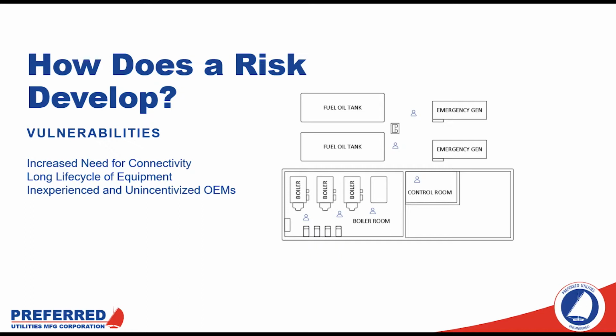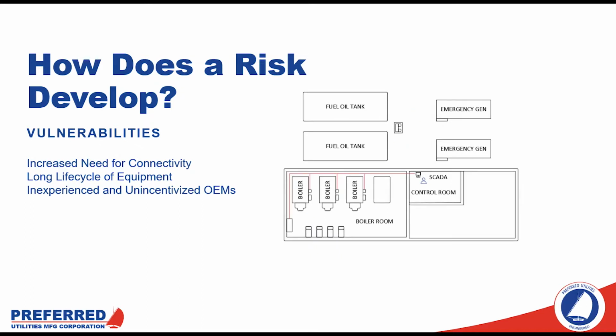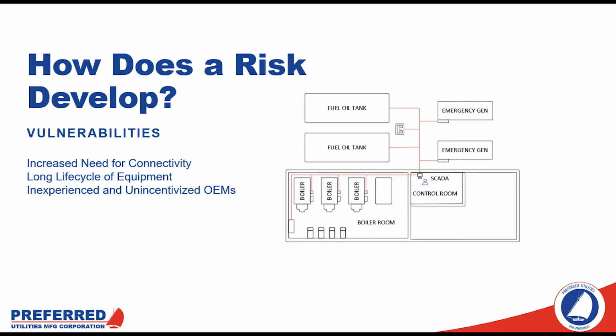What we often see happening is facilities, in order to reduce resource costs, installing SCADA systems, connecting up existing pieces of equipment so they can be centrally monitored from one location or by fewer people. As these control networks become more prevalent, equipment is getting rid of physical interfaces to command a pump to start or a fan to run, and these devices are starting to communicate over and rely upon these networks to operate.